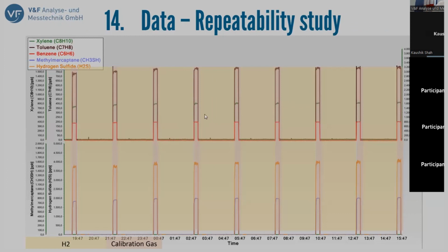And here is another graph, a repeatability study, where we used the same gas in order to demonstrate the stability of the instrument. Once it's calibrated, and this one is an application of the gas every 2 hours, you see that the concentrations are very reproducible throughout the day, as long as you do analyses. And calibration intervals we are also going to talk about a little bit later.